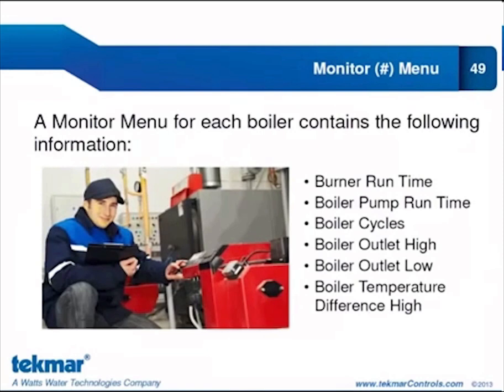In the 284, a monitor menu exists for each boiler, allowing you to have complete visibility over the operation of your heating equipment. The monitor menu for each boiler will contain the burner runtime, the boiler pump runtime, and both of these runtimes are in hours and they are updated every hour. Boiler cycles, boiler outlet low and high, and this is of course only applicable if you have an individual boiler outlet sensor, and the boiler temperature difference high, so this would be the maximum difference between the boiler inlet and the boiler outlet for that particular boiler.